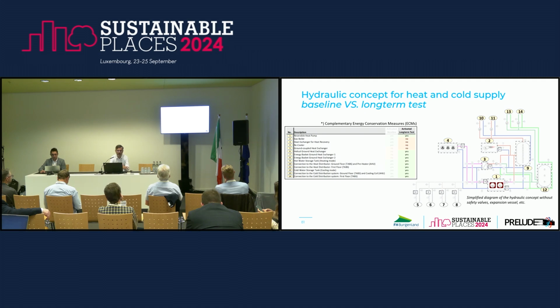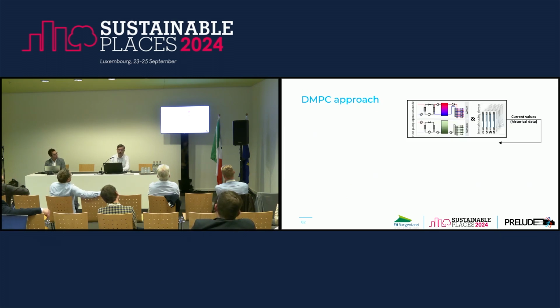And for the long-term test, before we started it, we made additional measures to save energy. So we switched off the gas boiler. We used the heat pump for space heating and space cooling. We also used some of the ground heat exchanger, so we don't use the recooler on the roof of the building. And we also switched off the reheater of the air conditioning system to avoid non-critical energy consumption in the summer months. So these are additional measures we have to consider if we look at the results of our long-term test.